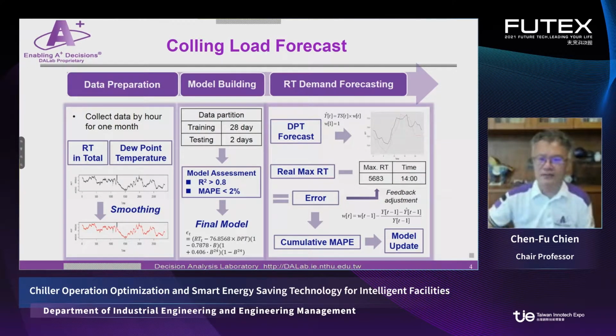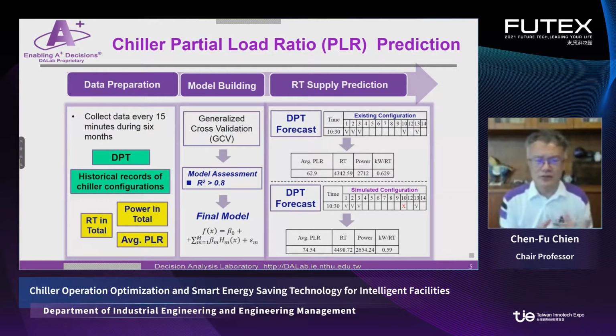So we can forecast the profile of the cooling loading. As I mentioned, not all chillers operate at maximum loading, because operating at maximum loading may not be so safe. Each chiller has an optimal control window for the partial loading ratio. So we try to utilize the best performance zone for each chiller, and together they generate enough RT demand to fulfill the cooling loading demand.